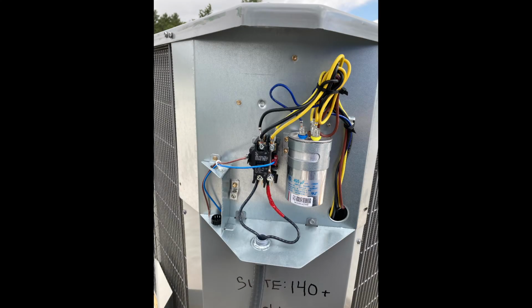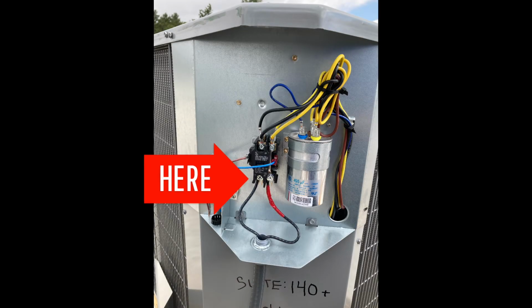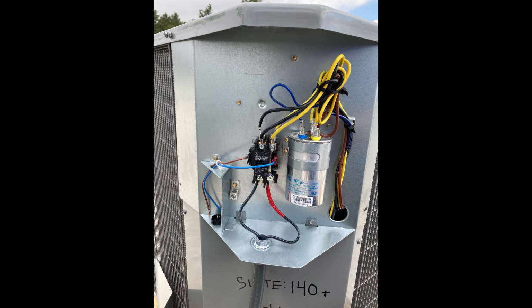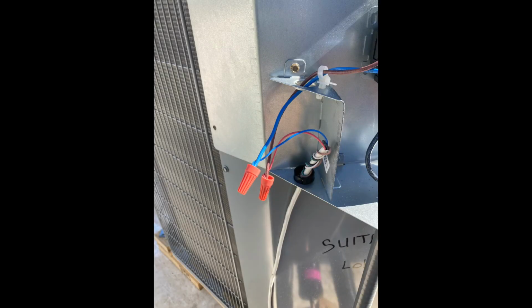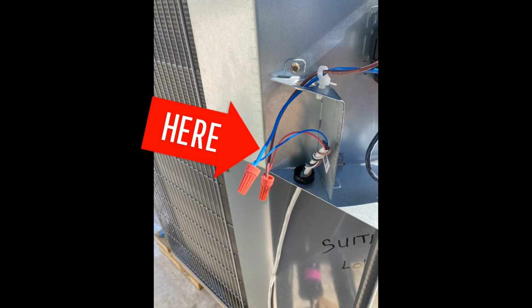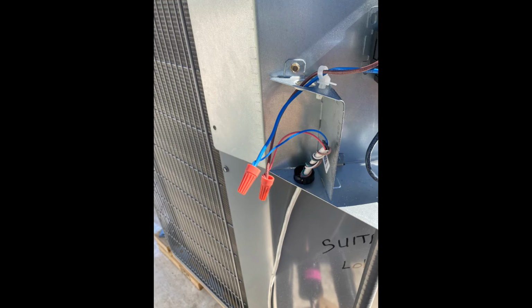So with the condenser placed on the roof, the power is still off. We go ahead and connect our high voltage to the contactor, as you see. Next, we'll connect our low voltage 24 volt thermostat wires. So these two wires run down to the first floor air handler to the control board. And on the circuit board where your thermostat terminals are, the blue wire connects to the common terminal, or the C terminal. And in this case, we're using a red wire, which would connect to the yellow terminal on the terminal screws.